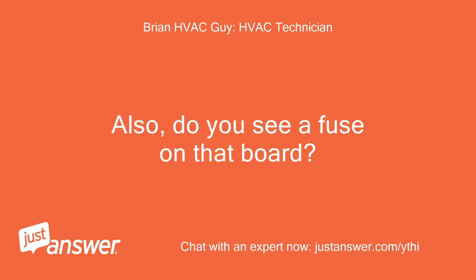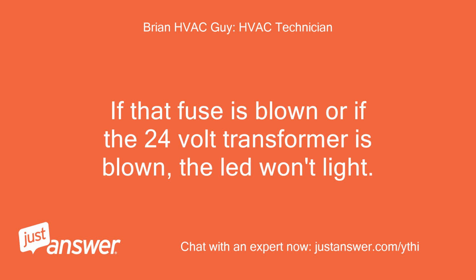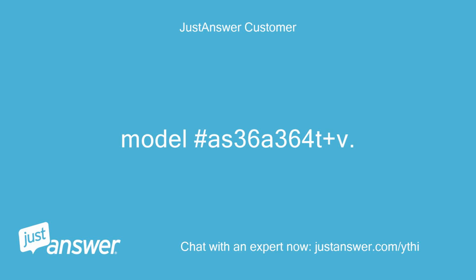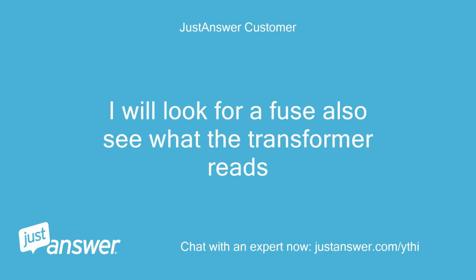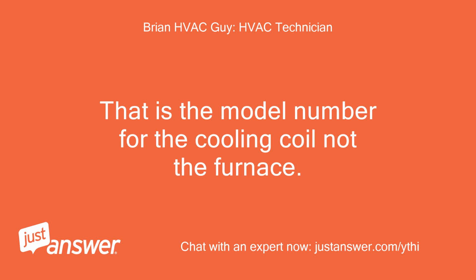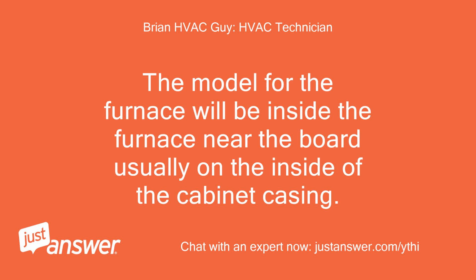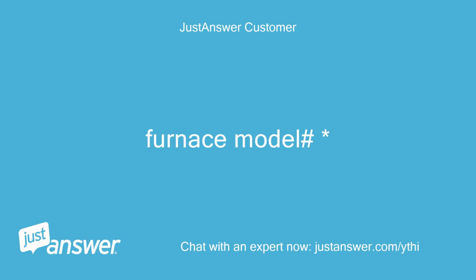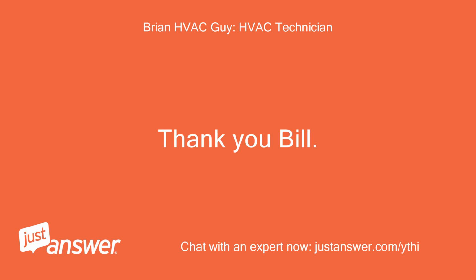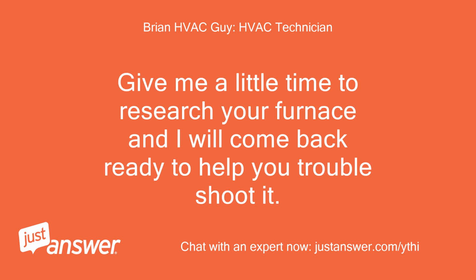Also, do you see a fuse on that board? If that fuse is blown or if the 24-volt transformer is blown, the LED won't light. Model number is 36A364T plus V. I will look for a fuse, also see what the transformer reads. That is the model number for the cooling coil, not the furnace. The model for the furnace will be inside the furnace near the board, usually on the inside of the cabinet casing. Furnace model number. Thank you, Bill. Give me a little time to research your furnace and I will come back ready to help you troubleshoot it.